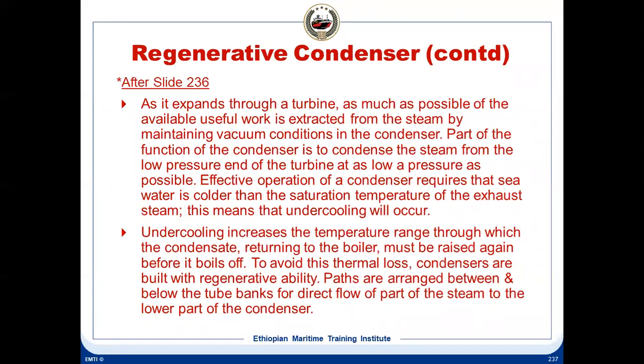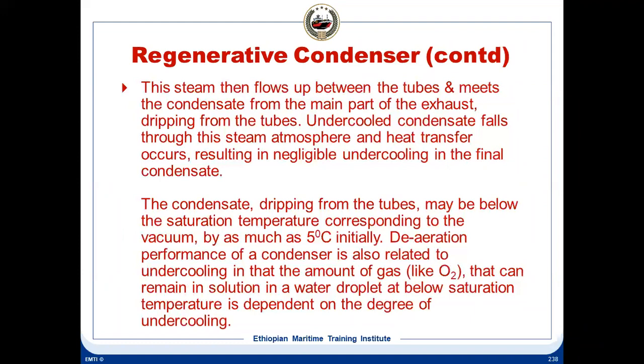And in the process of heating, the steam which is doing the heating also condenses, and again that becomes condensate. And since the temperature is pretty high, close to boiling point, close to saturation temperature, any gases which are dissolved in the condensate go off from the condensate and are extracted by the fan from the extraction duct.